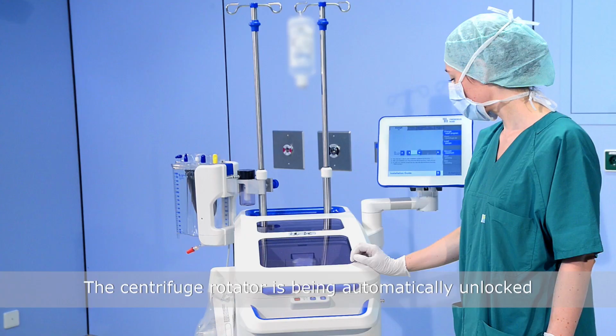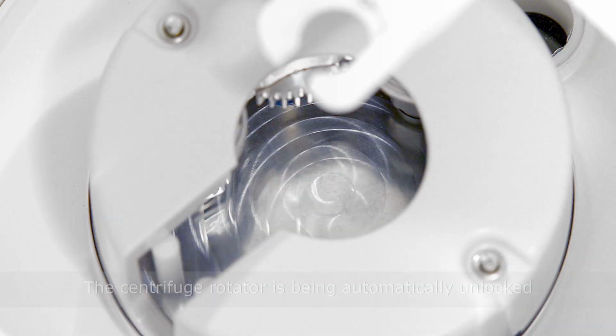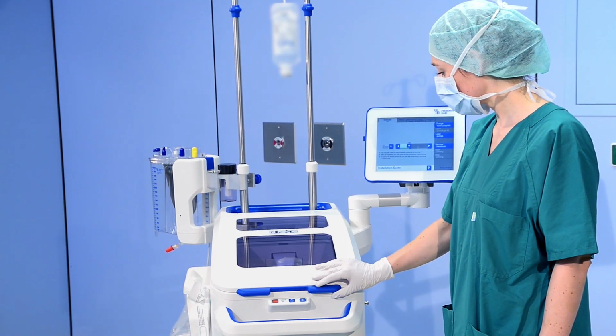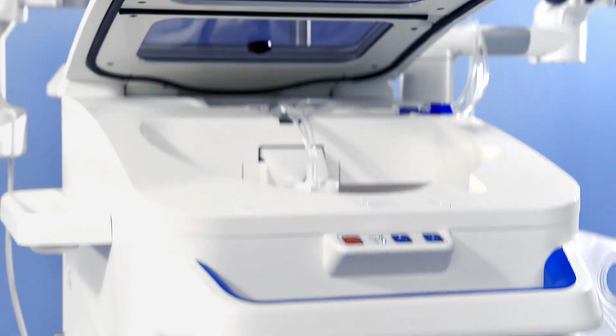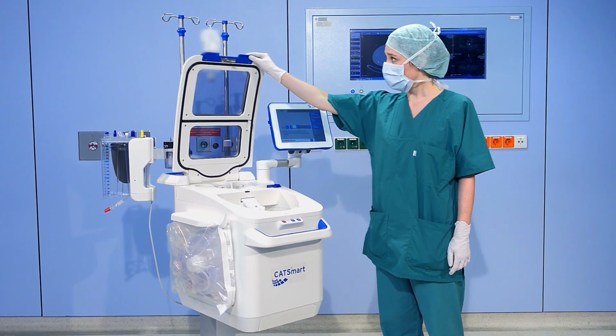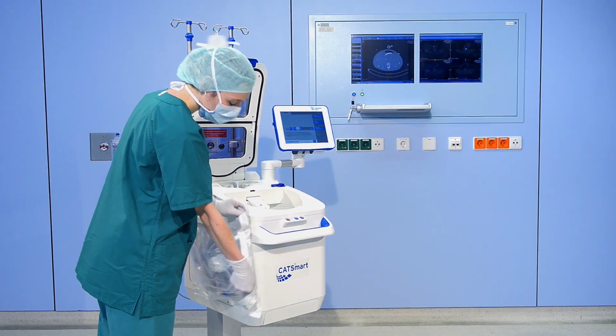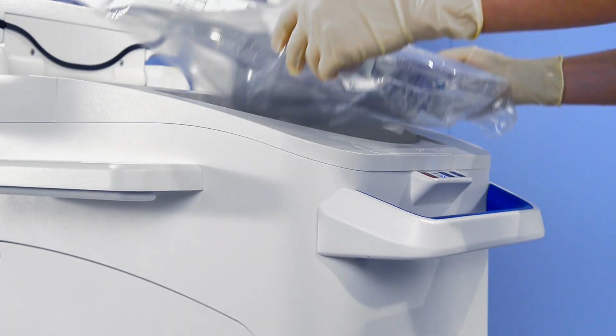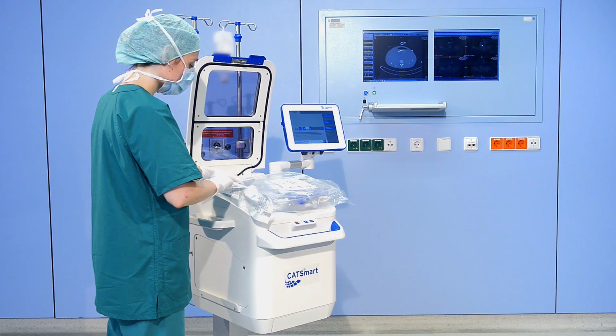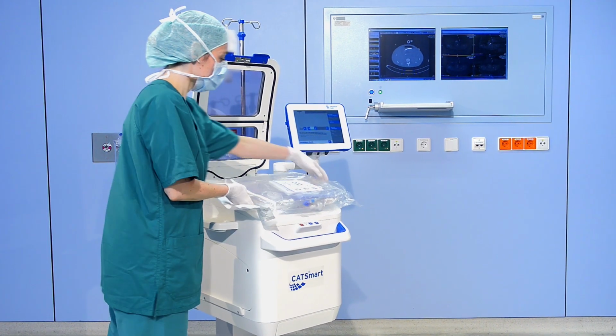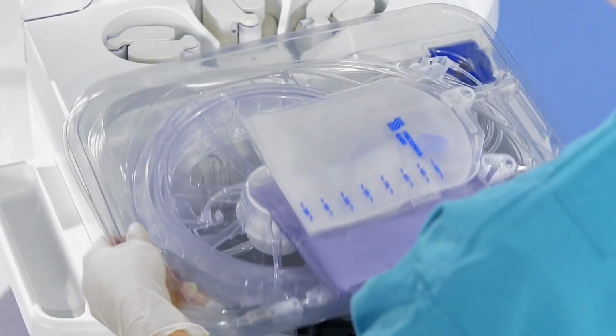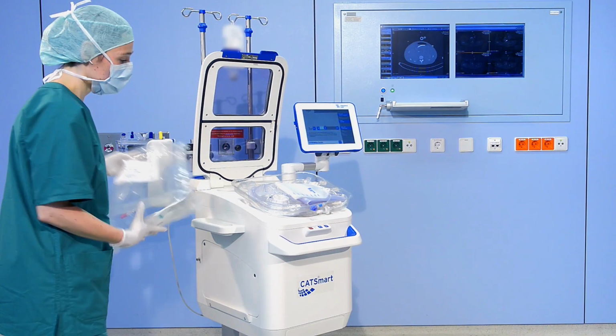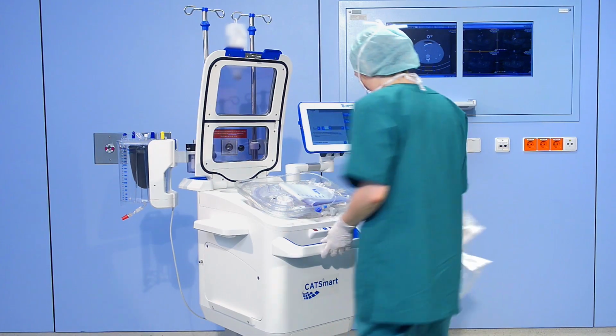Select the function Open Centrifuge Lid. You might hear the mechanisms as a confirmation and raise the centrifuge lid to the right position. Remove the packing shell from the packaging and place it over the centrifuge chamber with the Auto Transfusion Set. On the right side of the CATSmart device, there are special projecting elements for the packing shell on which the packaging tray can be placed.